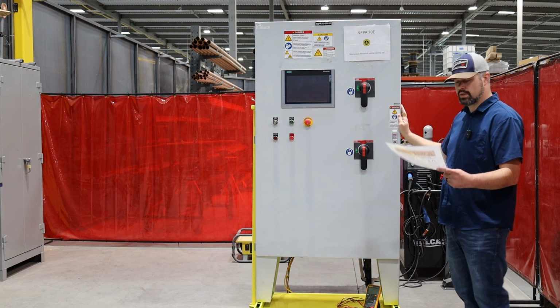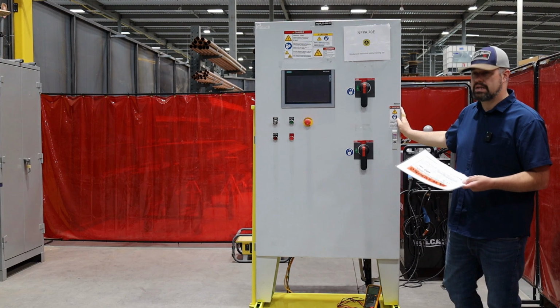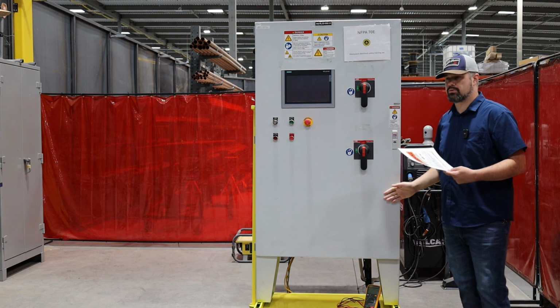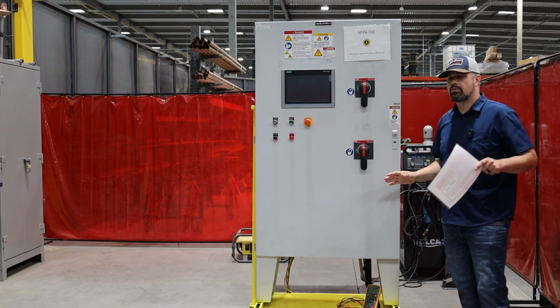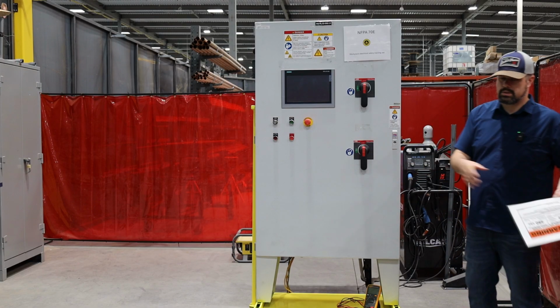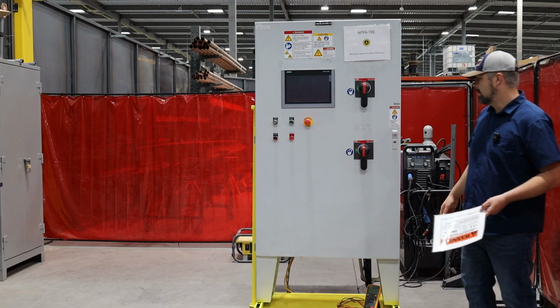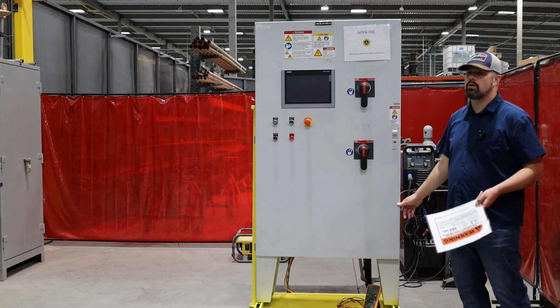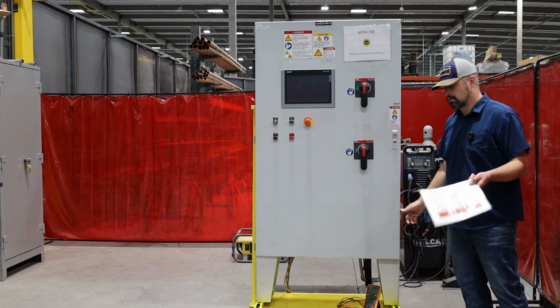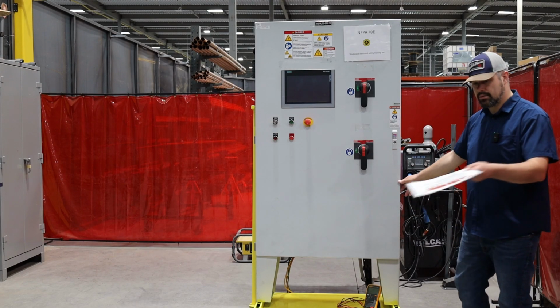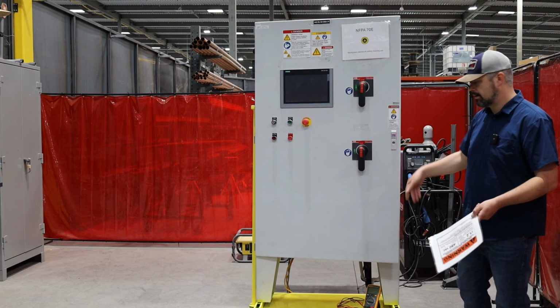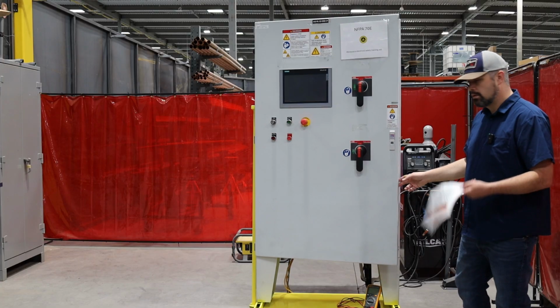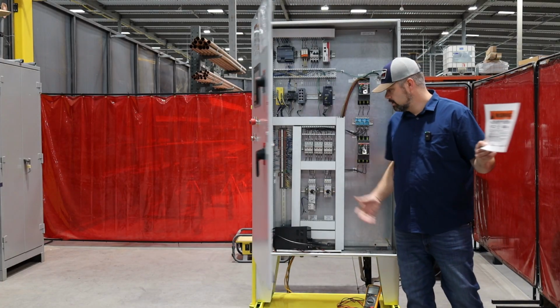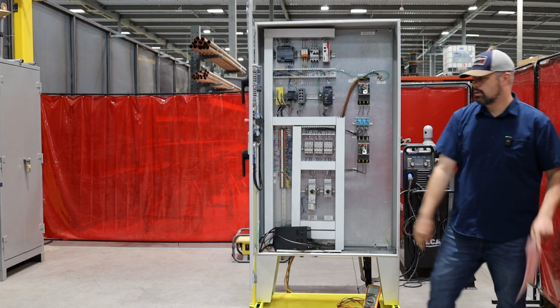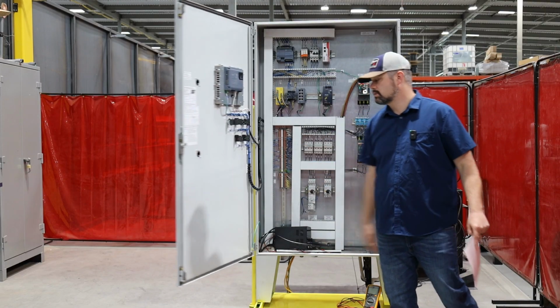So if there's any question, then you're simply going to wear the PPE you would need in order to be within that boundary, just to cover all bases. And again, this particular job, this company, we want to do that. We want to go the extra mile to guarantee everyone's safety, okay? So again, we've got our physical barrier up and the right PPE we need to be within the 18 inches of 1.2 cal or below for any exposed electrical conductors in here.